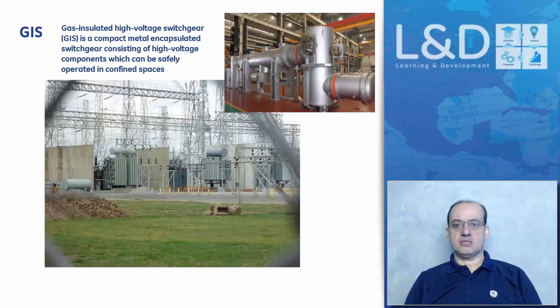The gas insulated system, of course, has its advantages because it comes in pre-built compartments, and that means it's optimized and it has a compact design. These pre-built compartments minimize the civil work, so that's a first advantage. The second advantage is that it has enhanced control and monitoring capabilities, so Ethernet can be built into these compartments, which means less wiring at the substation for substation automation achievement.